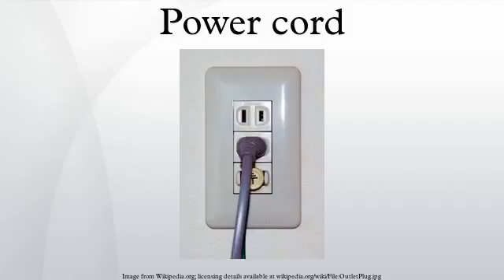Cords also have different types of exterior jackets available to accommodate environmental variables such as moisture, temperature, oils, sunlight, flexibility, and heavy wear. For example, a heating appliance may come with a cord designed to withstand accidental contact with heated surfaces. Worldwide, more than a dozen different types of connectors are used for fixed building wiring. Products sold in many different markets can use a standardized IEC 60320 connector and then use a detachable power cord to match the local electrical outlets. This simplifies safety approvals, factory testing, and production, since the power cord is a low-cost item available as a commodity.